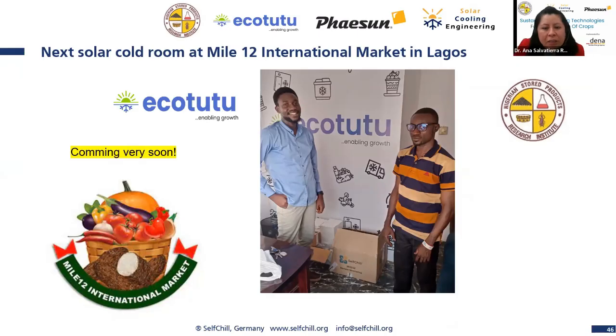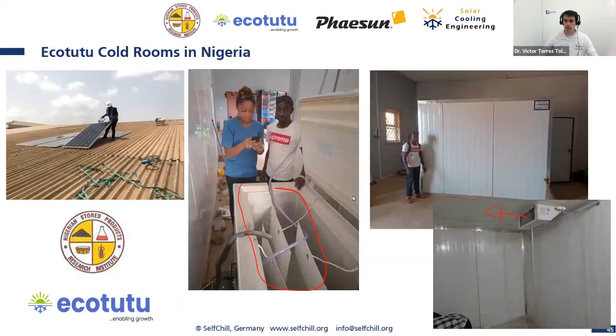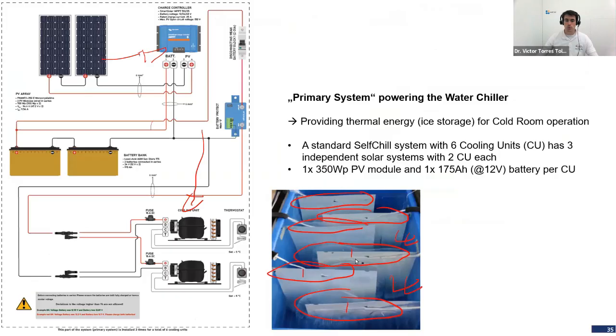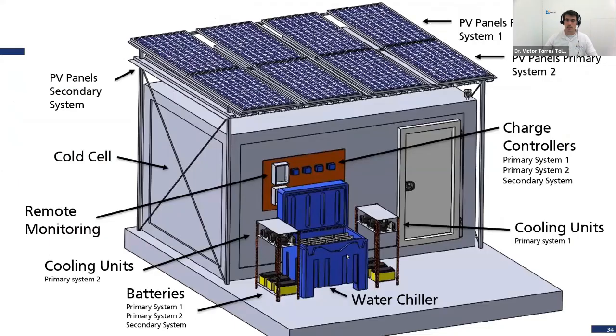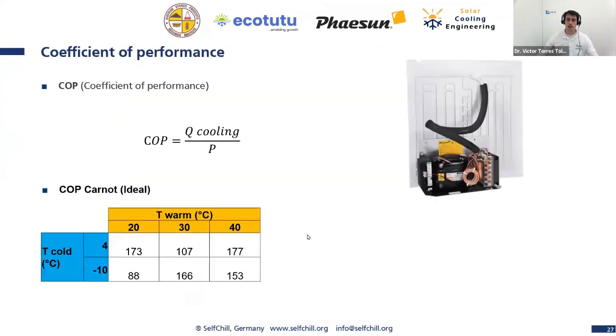But there is another question. Yes, there is another question: the cold water that goes into the cooling chamber, is it in water form, droplets or mist? What changes it to vapor in the cooling chamber? Okay, there is this question, yeah. What we have here in the water chiller is really water, yeah, just water and nothing else. Don't confuse it with the refrigerant inside the cooling units, right? So the cooling units, they have a closed circuit.